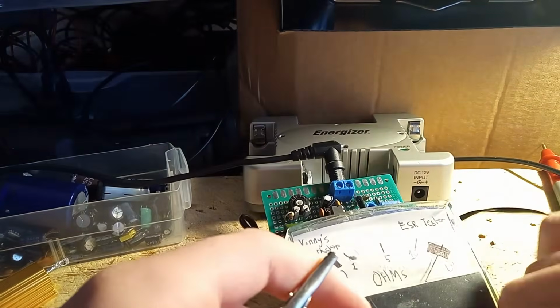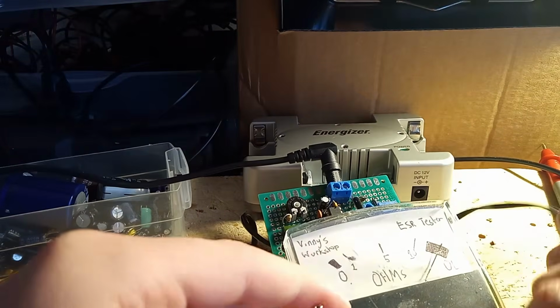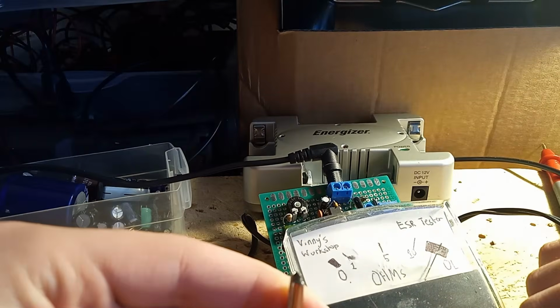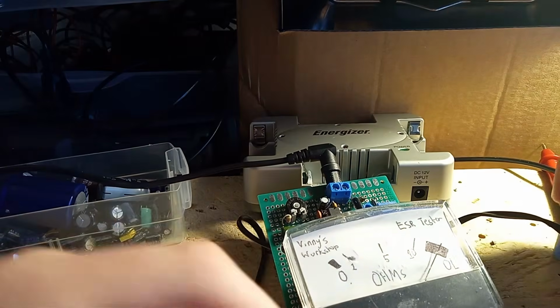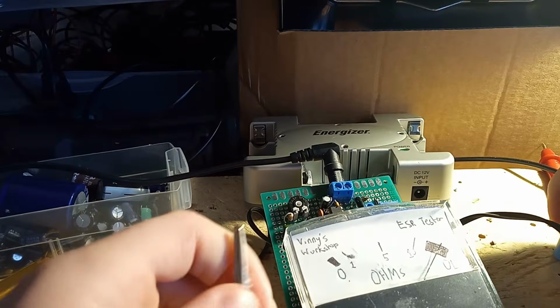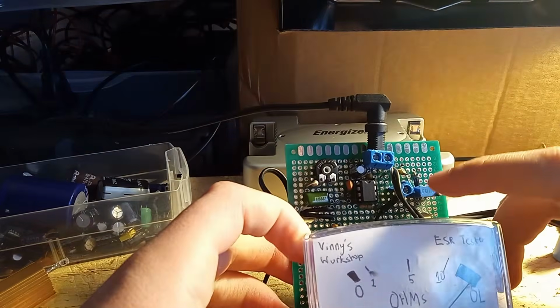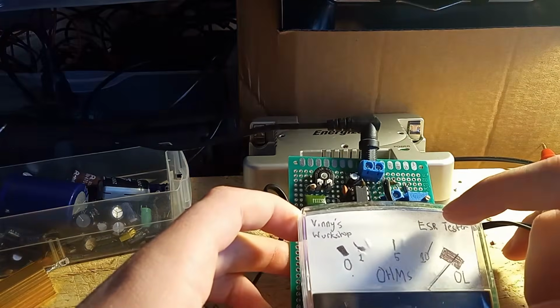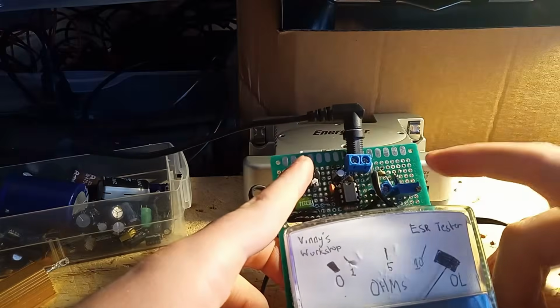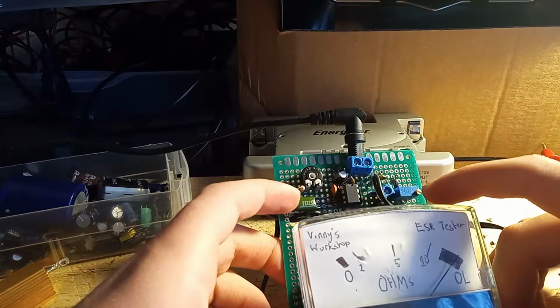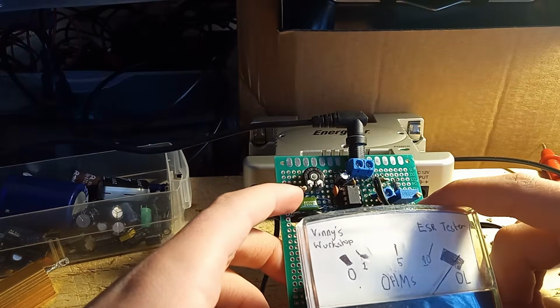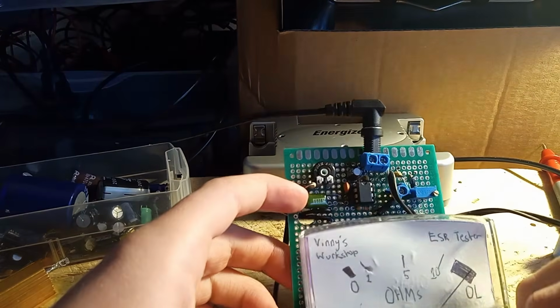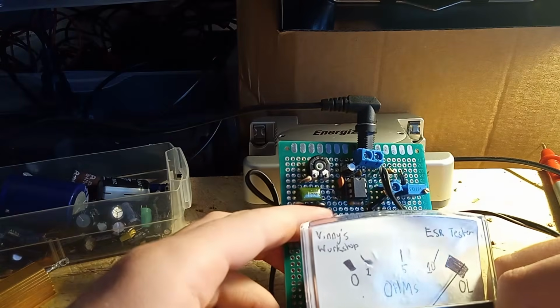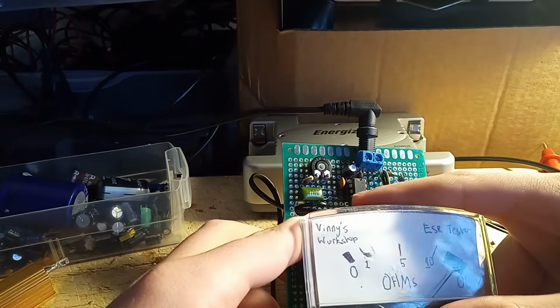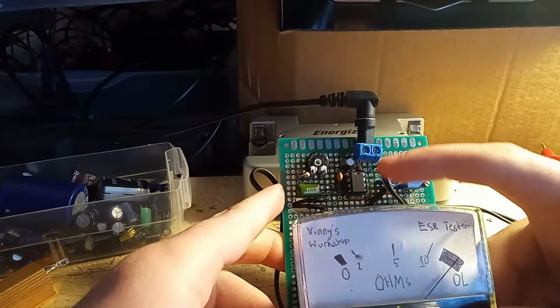It sends it out to the capacitor, and then the voltage drop of that signal is measured when the capacitor is connected up. A higher voltage drop means a lower resistance and closer to a short circuit, and it is measured by the meter, of course, which measures the current, and some resistors adjust the voltage threshold and the sensitivity and stuff. And there are some capacitors in series to filter out any stray DC, because this thing is basically just an input turning on and off, and we want a pure AC signal from this.